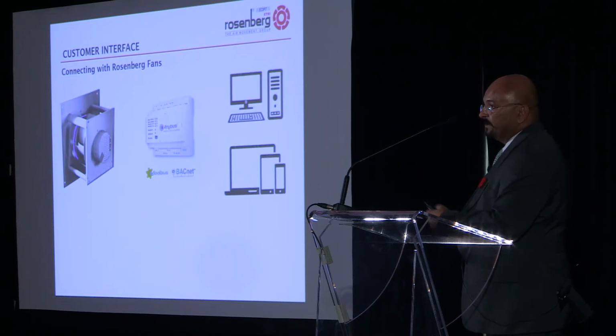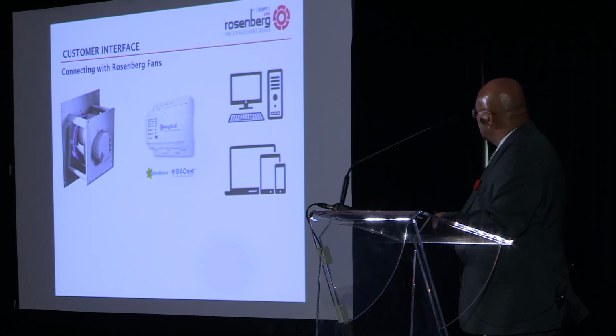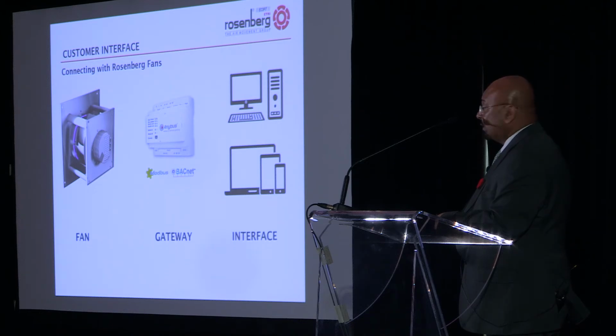The other feature we have is that you can connect these fans with the building BMS system, which is BACnet. We can provide a gateway as well. We have the Modbus interface, so it will communicate with Modbus and convert the signals to BACnet. So we can provide that as well.